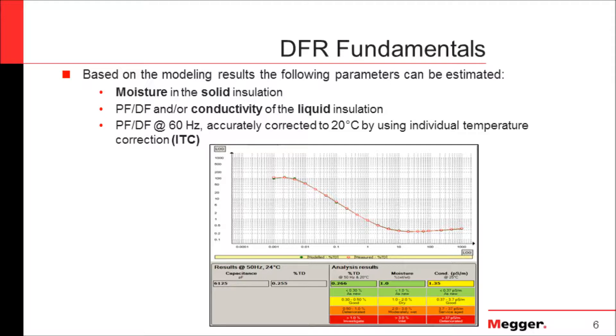Another goal is to look at the power factor at 60 hertz. We need to normalize the power factor value if we run the test at a temperature other than 20 degrees C, in order to enable trending analysis in the future. With DFR technology, this normalization has been improved. We now use what is called the Individual Temperature Correction, or ITC, which is a feature only provided by dielectric frequency response.